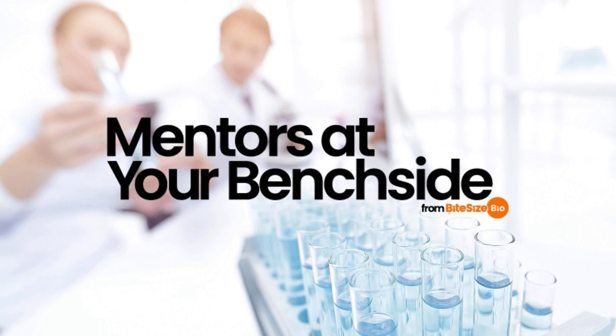And the first is the repeatability test. If the minimum weight capacity of your scale is 1 gram and the max is 100 grams, measure out a weight somewhere on the upper end of this, say 75 grams. You're looking for a weight value of about 50 to 100% of the weighing capacity of the instrument, so kind of in that top half.